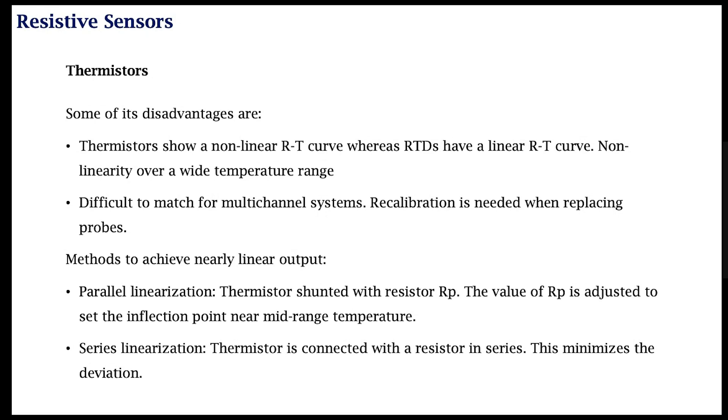They work well only within a relatively small range. Another approach to achieve linearity or nearly linear output is to use parallel linearization by using a parallel resistor, shunting it with a shunt resistor. This value of Rp is then adjusted to set the inflection point at the mid-range temperature.